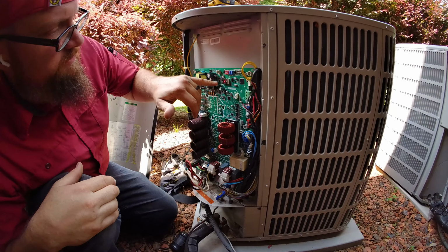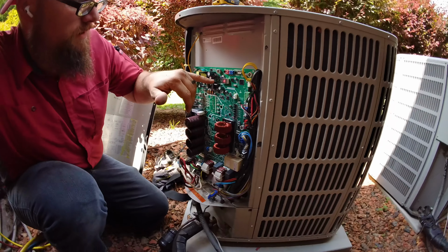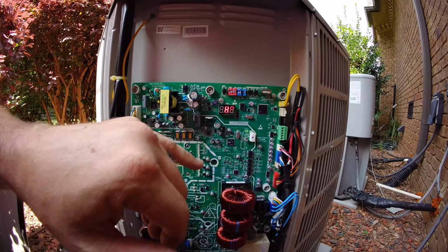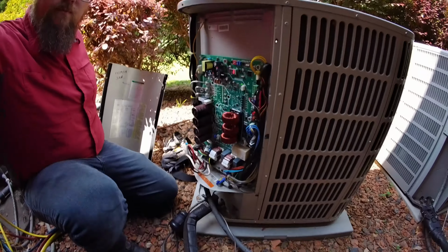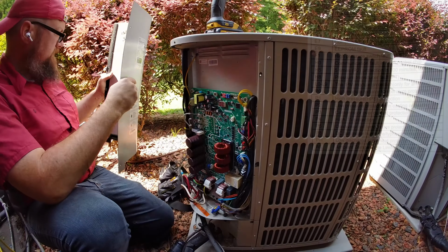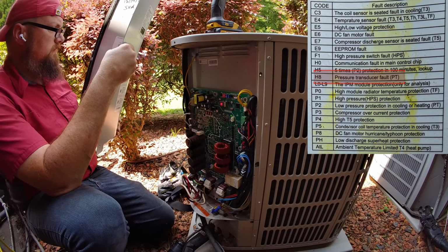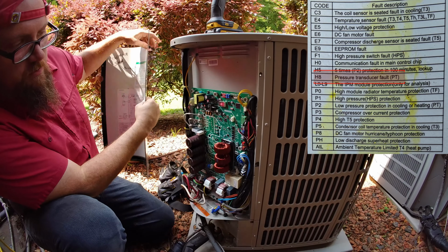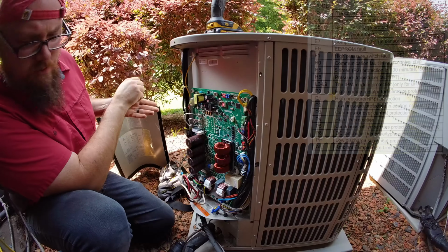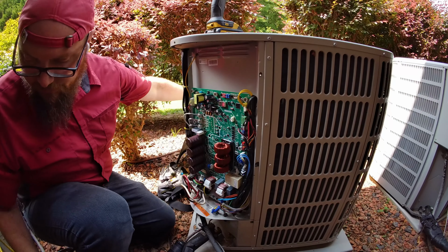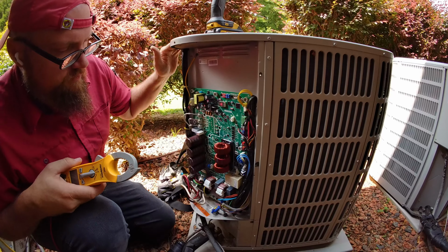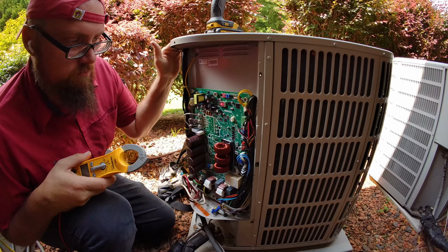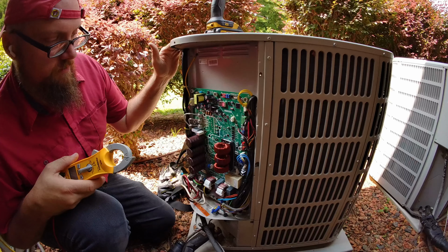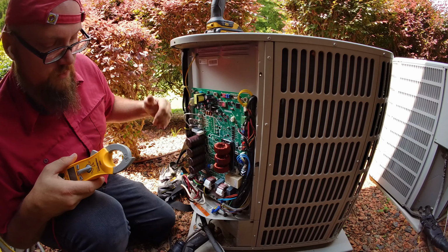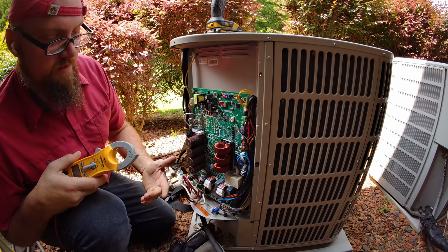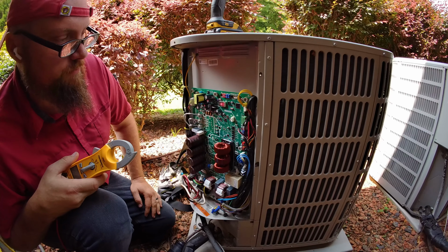Alright, what we see immediately is an H8 error right here. And I believe on these Bosch units, if I recall, that is a pressure transducer fault. So how you actually troubleshoot pressure transducers, and if you can imagine, these units are doing much the same that our gauges do. It's actually watching the ambient outdoor temperature, the coil temperature, our temperatures on our lines, and the pressure transducer is actually watching the refrigerant pressure.